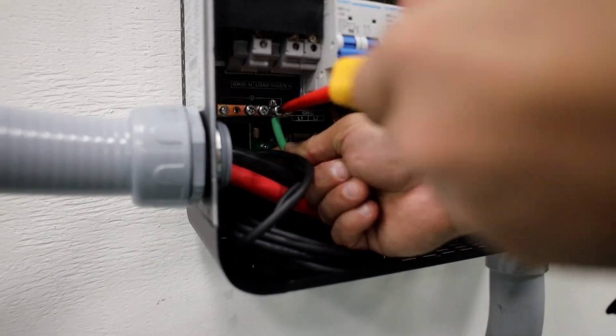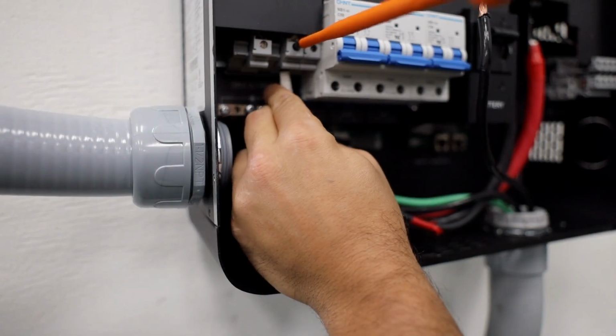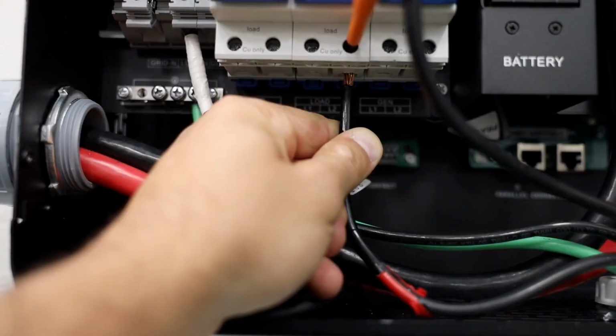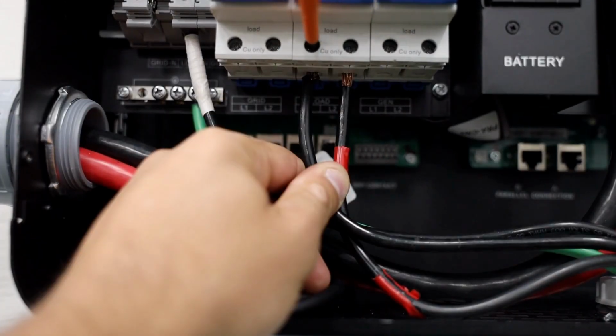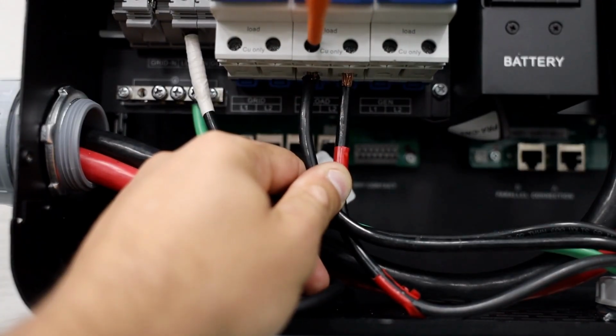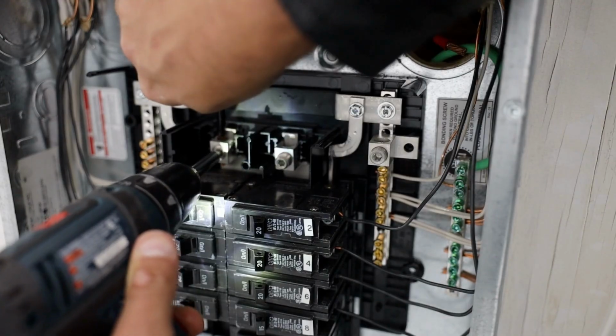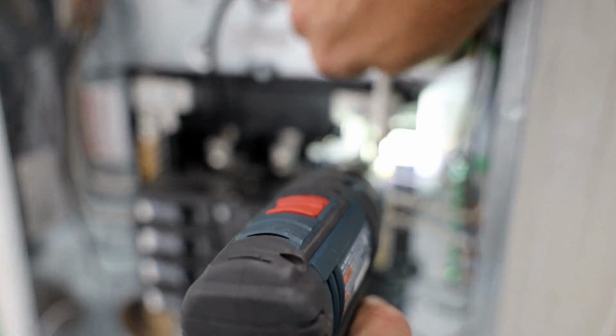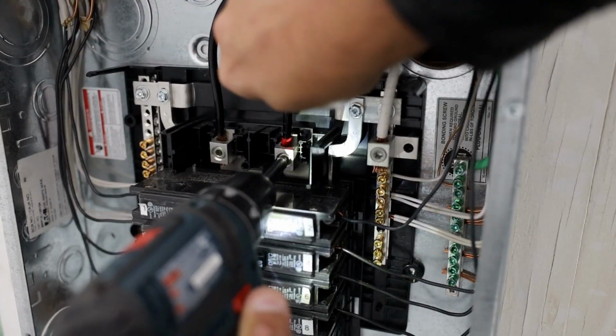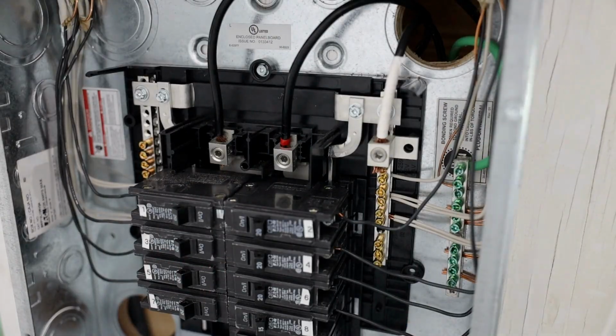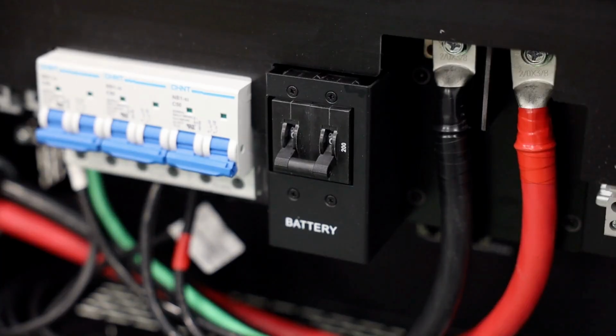Begin by connecting and securing the ground, neutral and line conductors to the inverter. Ensure that all terminations are tightened in accordance with the manufacturer's specified torque values. Finally, secure the conductors to the load panel. When routing the cables, avoid sharp bends, as excessive bending can damage the conductors or compromise the insulation.